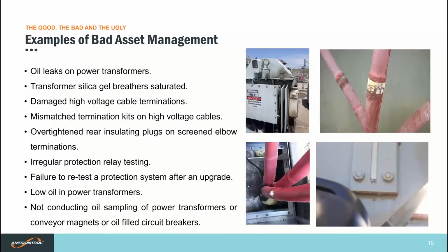Just to sidetrack again for a moment, low oil levels can cause a trip when the temperature drops. Oil leaks have both an environmental and operational impact. Regular oil sampling can give quite a large overview of what is happening inside that big grey box. Simple, basic insulation and polarization index tests are very beneficial to give you an indication without opening up the transformer. The PI test is a big one we use, and it can provide information on the moisture and deterioration of the winding insulation. The test is a 10-minute to 1-minute ratio, an acceptable value being at least 2 or higher.